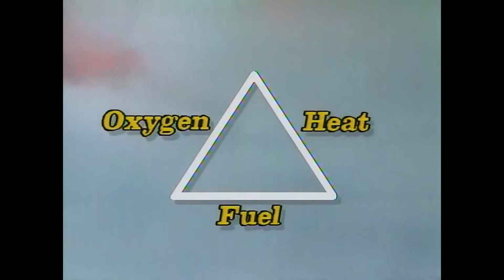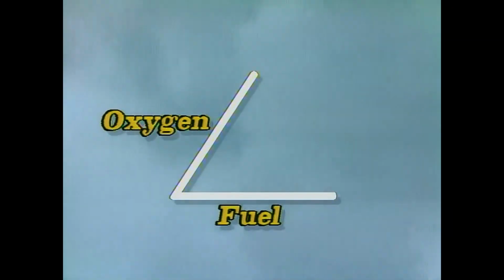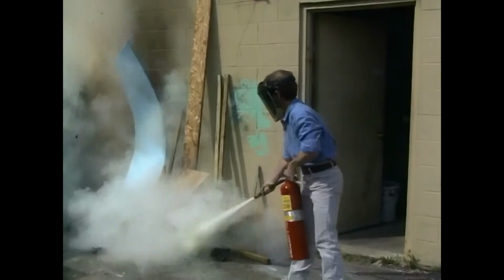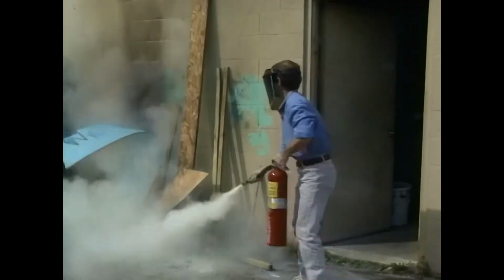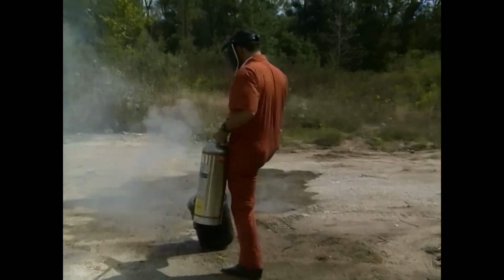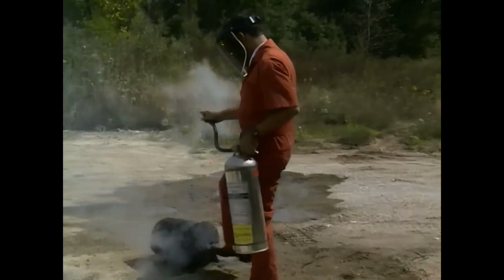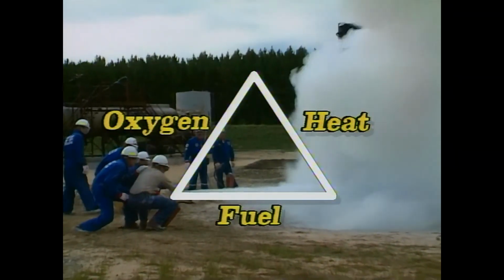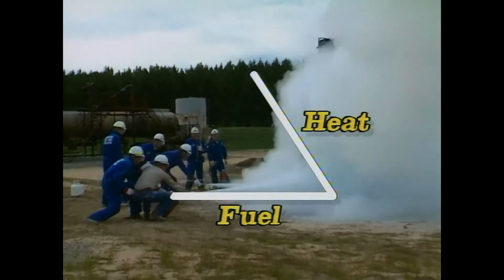The water in Class A extinguishers removes the heat element of the fire. Class A fires form embers that will continue to smolder if unchecked. Always make sure a Class A fire is totally extinguished and remove the materials from the building after they are extinguished. Class B extinguishers work by smothering the fire or removing the oxygen.